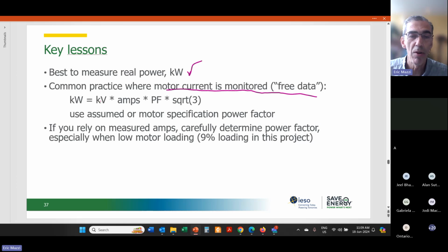And all we need to get real power for these induction loads, like an induction motor, is to come up with a realistic power factor. And in many cases, that can be done. However, in this particular case, the power factor was way overestimated. The power factor was assumed to be 0.8, just based on experience, and the measured power factor was 0.25.